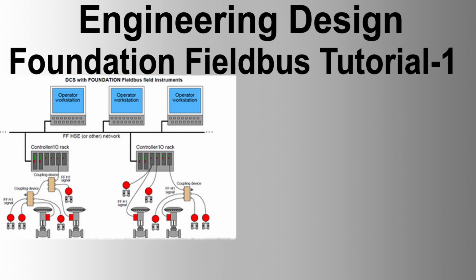Link Active Scheduler, LAS, controls the medium access. Foundation devices are classified with device classes: Basic, Link Master, LM, and Bridge. A LM class device can work as the LAS, while Basic class devices do not. A Bridge class device has, in addition to LM capability, the functionality to connect links. One and only one device in a link works as the LAS. At least one LM or Bridge class device is needed in a link. LM devices try to acquire the LAS role when no LAS exists on startup or when the current LAS fails. The LM device with the least node address wins this contention. Other LM devices observe the LAS activity and take over its role when LAS goes away.